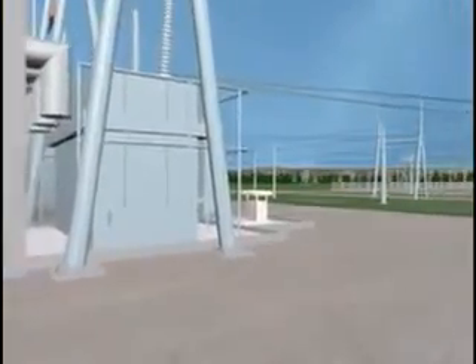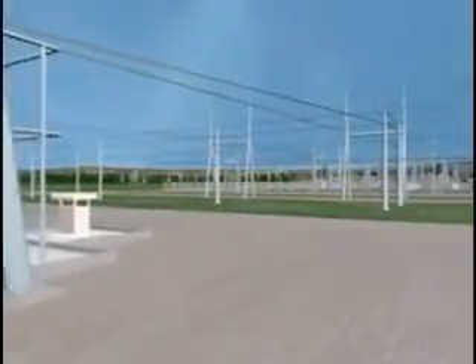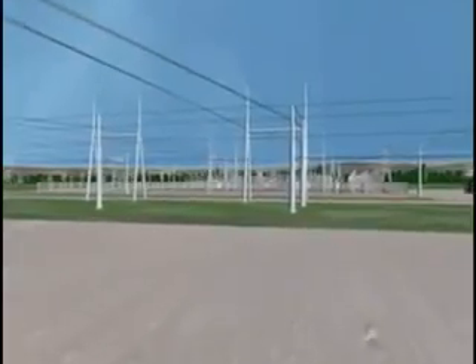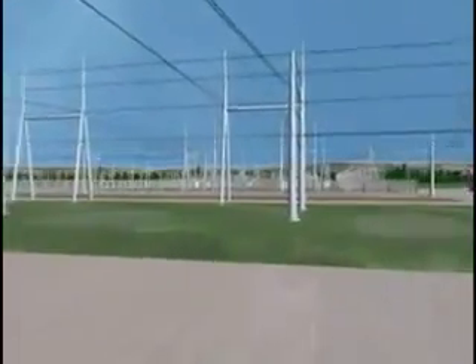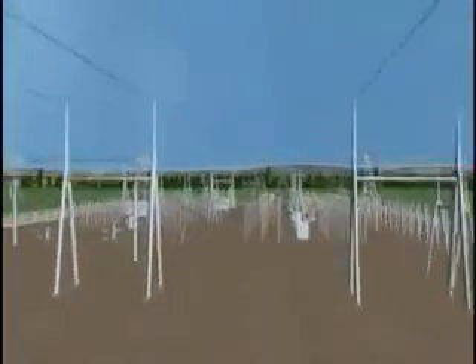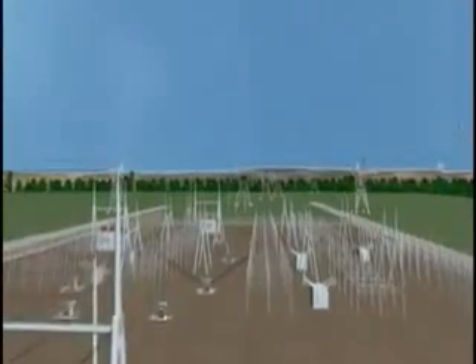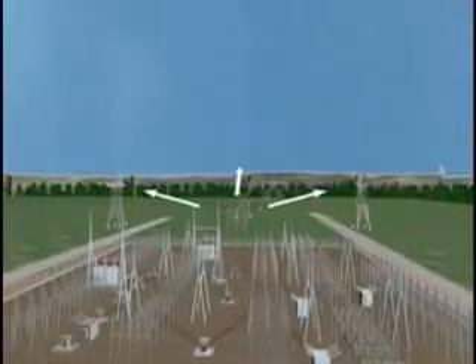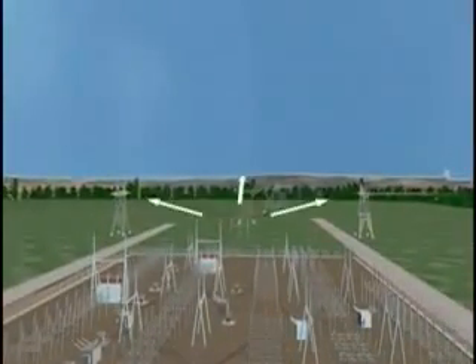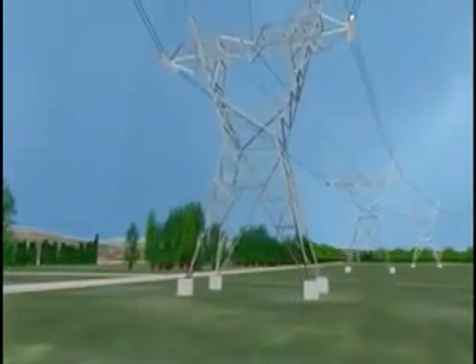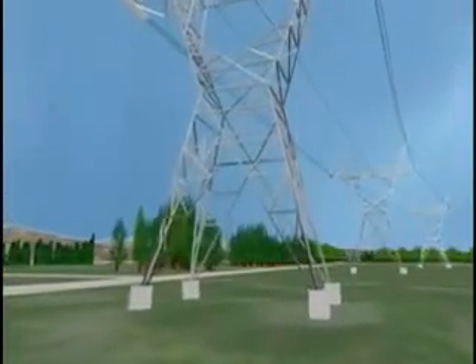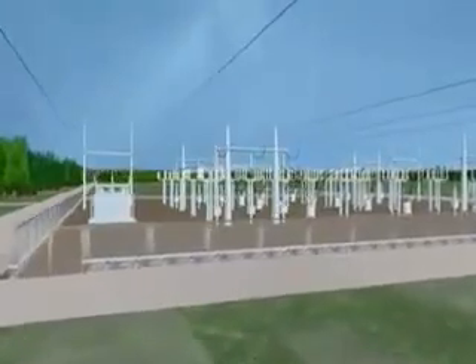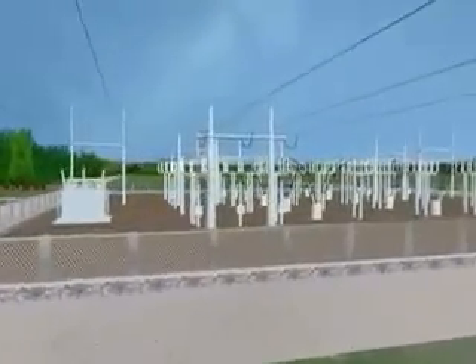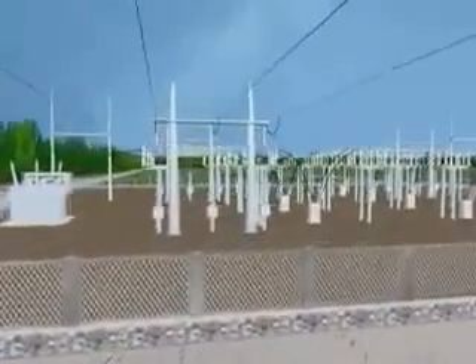At the step-up transformer, the voltage is increased from 24,000 to 345,000 volts. Electricity flows through the switchyard that determines the transmission line or path. Electricity is like plumbing. Where you turn the water on is where the water flows. Electricity is pulled to the source where it is needed. At the substation, voltage is lowered so it can be moved across utility poles.